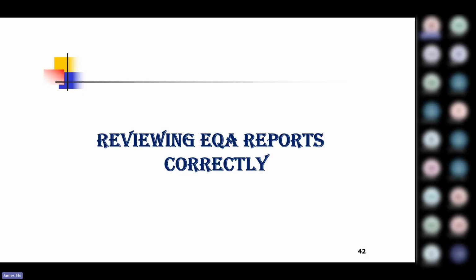As we run close to the closing stages, I want to look at reviewing EQA reports correctly. As I said, a lot of people pick up an EQA report and they don't really know what to look out for. The only thing a lot of people know is: is my result within 2SD? Even if it is at 1.99 SDI, they say I am fine. You are not fine. If you have not been operating in that region, why are you accepting 1.99? You've been running at less than 1 in the past 10 months. Why do you want to accept 1.99 in this 11th month? That is where you need to understand what to look out for in reviewing EQA reports.